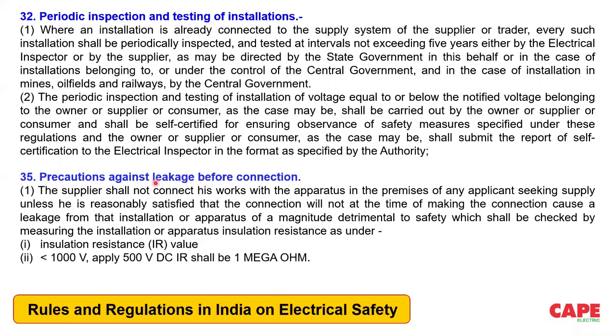Then precautions against, I'm just showing you some of the regulations which are very much connected to safety in an electrical installation. For example, I have put the new numbers. I think the earlier numbers were 30 and 33. Now the new numbers are 32 and 35. Regulation 32 talks about periodic inspection and testing once in 5 years. Regulation 35 talks about precaution against leakage before connection. This regulation says before you connect electricity to a consumer premise, you have to make an insulation resistance test, and the value shall be higher than 1 megaohm. Unfortunately, these tests are nowadays not carried out at all, and this is one of the reasons for accidents.